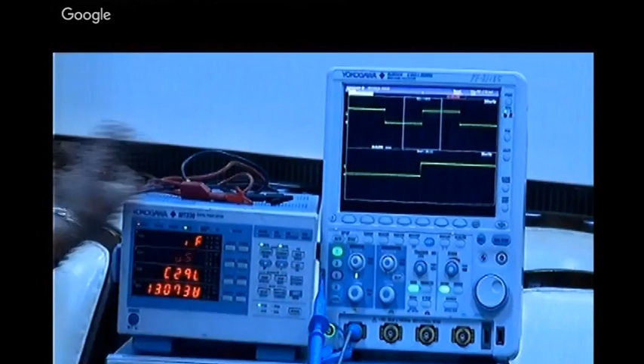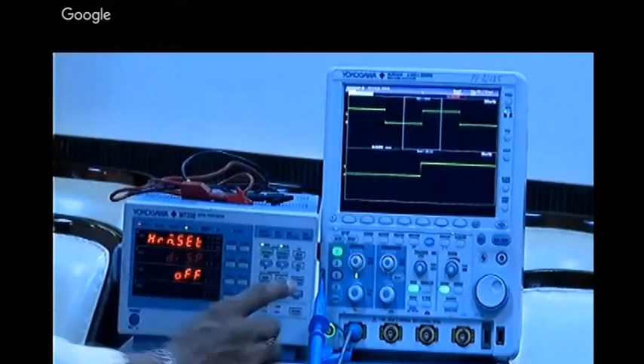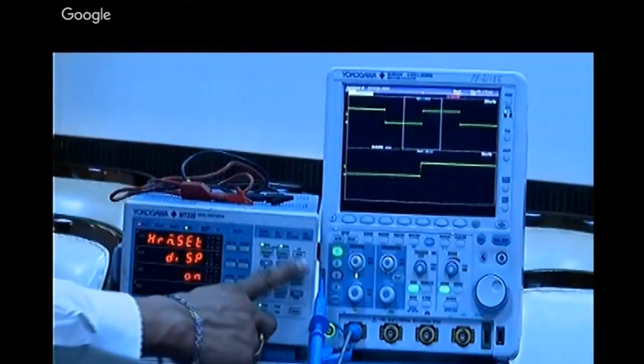Update after how many seconds you want the data. From 100 milliseconds to 5 seconds, you can set it here. Let's say 5 seconds also. Then interface connectivity, GPIB or USB or Ethernet, you can configure here. USB is automatically detected by the computer. If it is harmonics, it can show up to the 50th order harmonics. The order you can see, then by the up and down arrows you can see the values also.